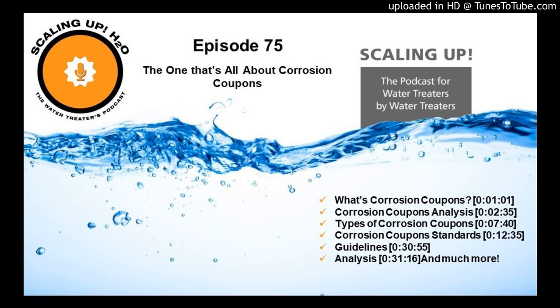Well, now let's say that corrosion coupon is pitted. Even though it weighed to where it said it was good, pitting is never good. Pitting is never acceptable. So when you look at the rates on what is acceptable and what is not, you have to remember that pitting is never acceptable. Now, here's what pitting is. Here's how I like to define pitting.